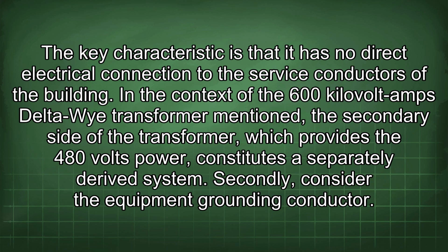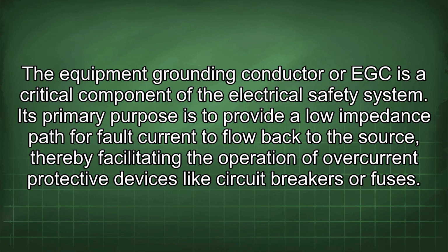In the context of the 600 kVA delta-Y transformer mentioned, the secondary side of the transformer, which provides the 480 volts power, constitutes a separately derived system. Secondly, consider the equipment grounding conductor. The equipment grounding conductor, or EGC, is a critical component of the electrical safety system. Its primary purpose is to provide a low impedance path for fault current to flow back to the source, thereby facilitating the operation of overcurrent protective devices like circuit breakers or fuses.